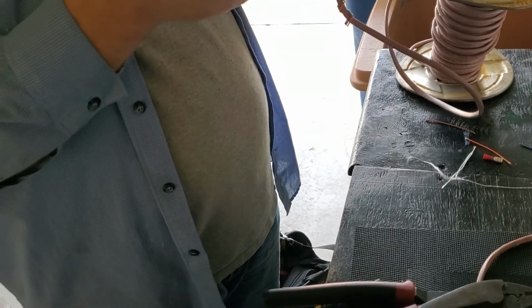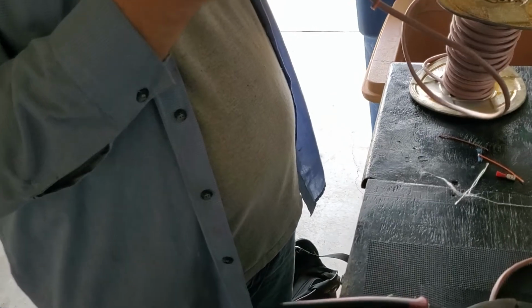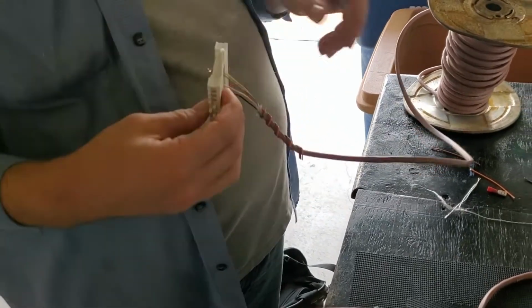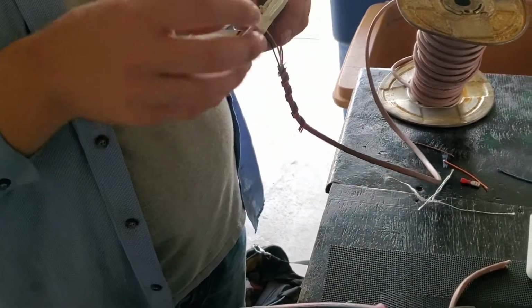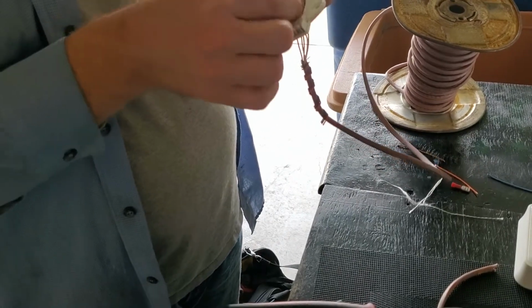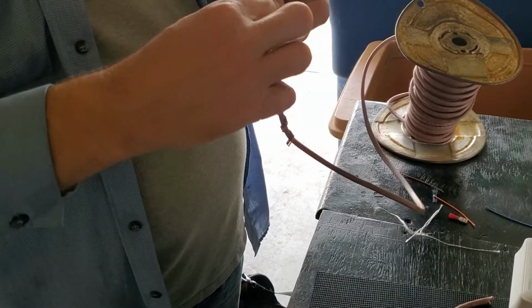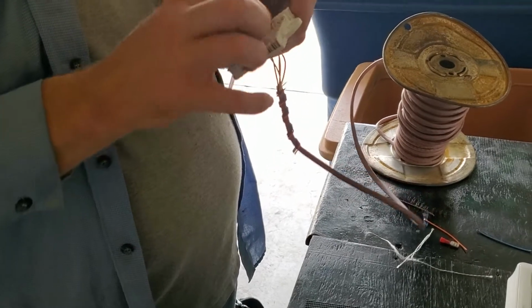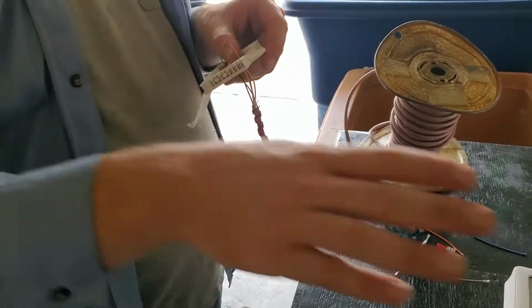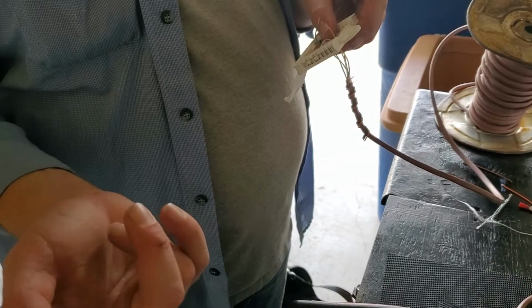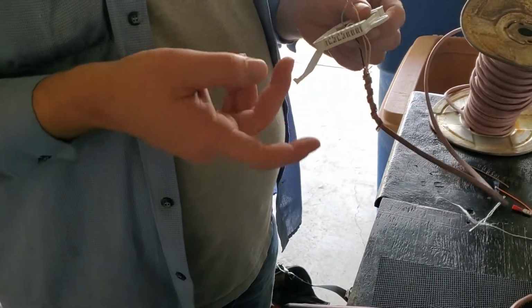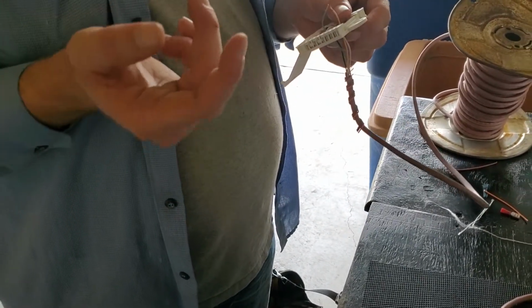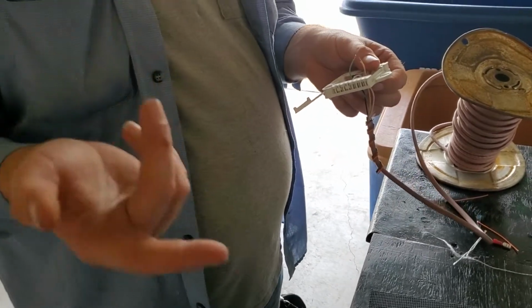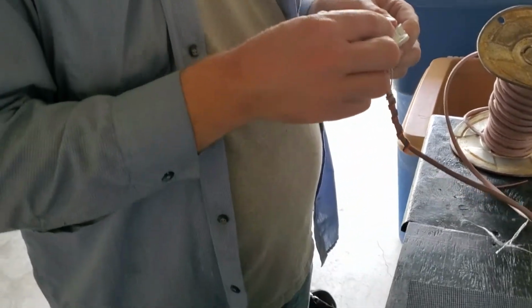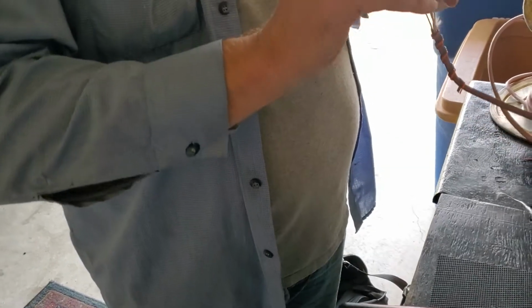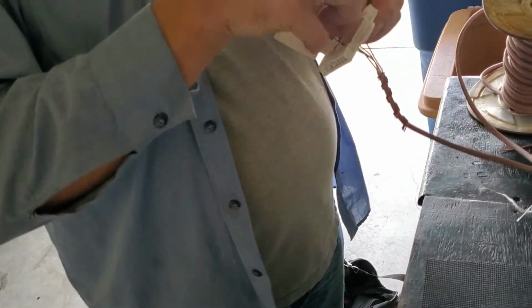Usually, if they're not on the cheaper end, they'll use an 8 conductor, and you always have extra wires available. Yeah, I've seen people just do 4s. That's where you can get screwed sometimes, and that's why I'm telling you to have a roll of thermostat wire, because the price you offer is installed—it's a turnkey price. If you have to pull in thermostat wire, that's on you.